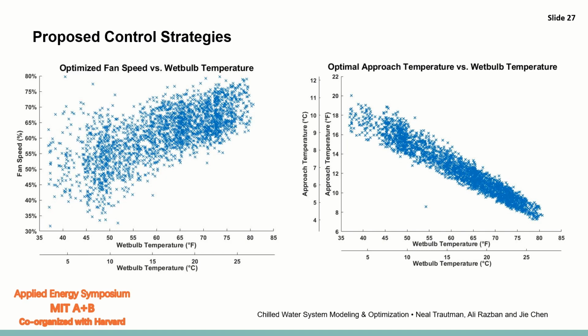So the graph on the left was the fan speed versus directly from wet bulb temperature. The correlation we found was rather poor, whereas if we controlled the approach temperature versus the wet bulb temperature, we had much better correlation, which would indicate that it's a much better control strategy for this situation.